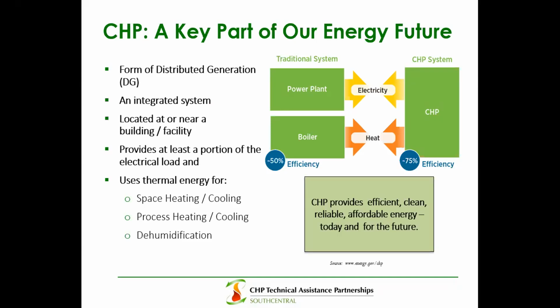The key benefit of CHP is that you capture the waste heat coming off that generator or turbine, and use it for a variety of purposes—cooling, heating, processing, sterilization, dehumidification, domestic hot water, steam, etc. This gives a higher efficiency system versus the traditional approach of a centralized power plant generating power plus a separate boiler, hot water heater, or chiller on site providing thermal or cooling service. Instead of those two separate pieces, the one CHP system provides both services at a more efficient and cost-effective rate.